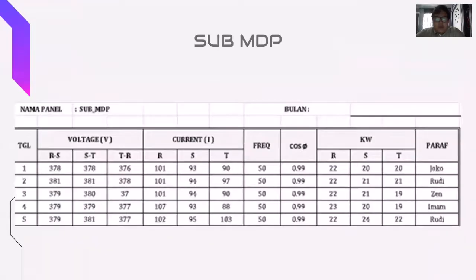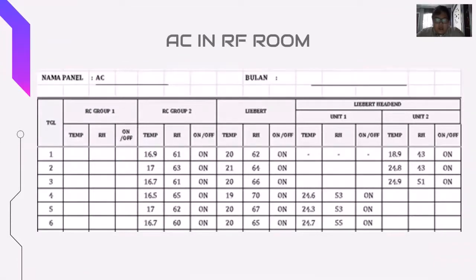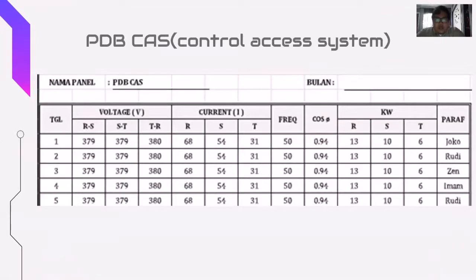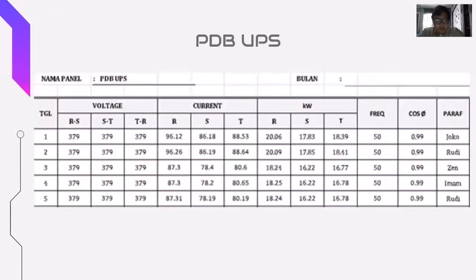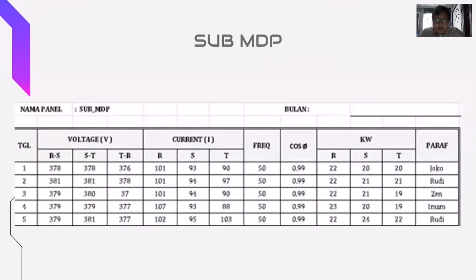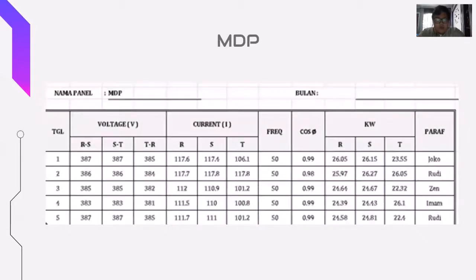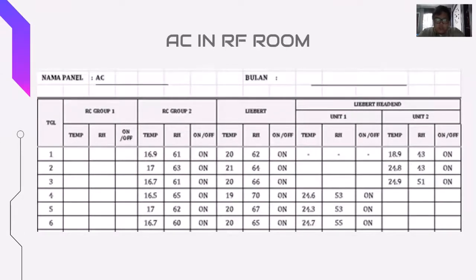The ATS AMF, the MDP, the sub MDP, the PDB UPS, the AC in the RF room, the PDB CAS control access system. You can see that they are basically the same, which is just checking the phase-to-phase voltage, the currents, the frequency, the cos phi, and the RST for each phase. The difference is in the AC, where we check the temperature so it does not get too high or too low, so there won't be any condensation. And you can see that the AC switches off between two units, so the AC won't get broken if one just continuously runs.